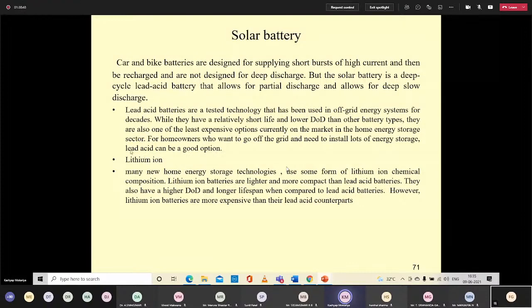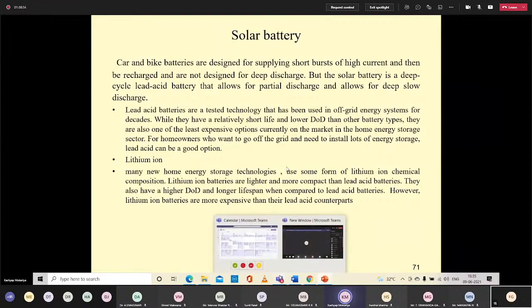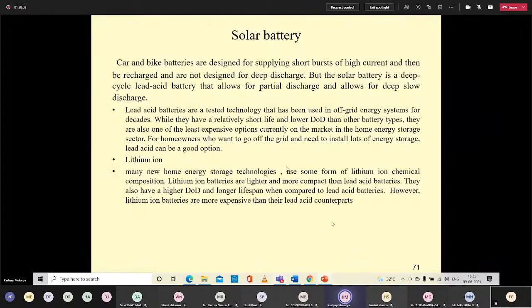I was working as a maintenance engineer at RIL Surat, Reliance Industries, where we did preventive maintenance of batteries. Lead acid batteries didn't last due to two reasons: first, they require maintenance; second, when there is spilling of liquid, H2SO4 and DM water mixed in the cells of typical lead acid batteries, the series connection of the internal battery gets cracked and broken.